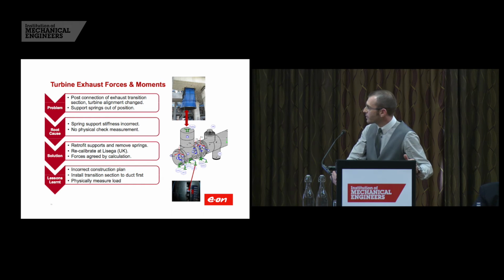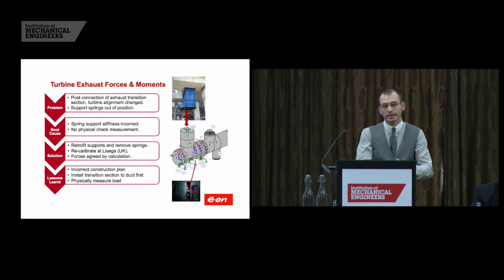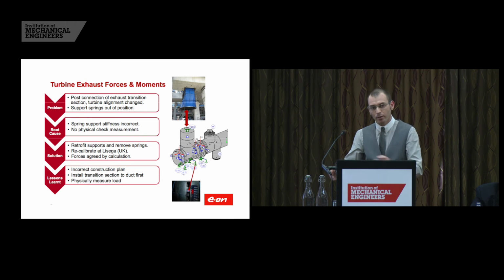There are two things. Tie up the termination points in the contract with the OEM manufacturer. The turbine was from Brazil, so that was one package of work. TGM Kanis in Nuremberg provided the exhaust duct, so their contractual termination points were slightly different. So in future, we need to ensure that any items like this are married up. But the erection sequence could have been slightly different.